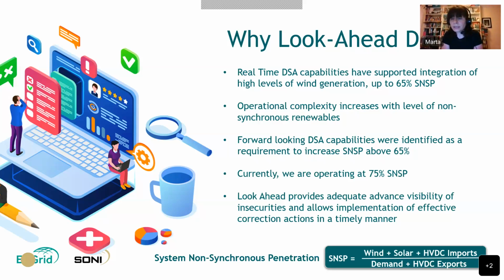As we increase the level of wind on an instantaneous basis, the number of corrective actions we can implement is reduced, as we displace conventional units with wind. And the time it takes to implement any remedial action is actually increased. It takes time if you need to bring a new synchronous generator online and up to speed. It also takes time if the remedial action is sectionalizing the network, changing the network topology. So all of those measures take a bit of time.